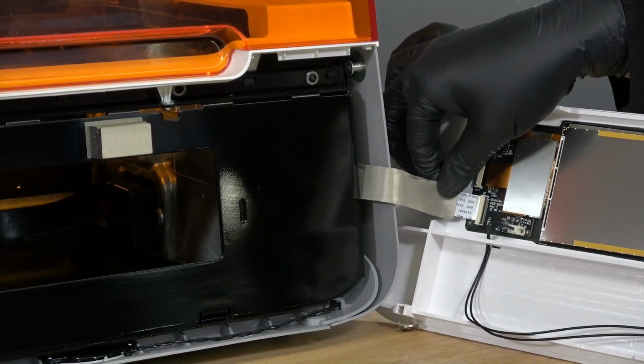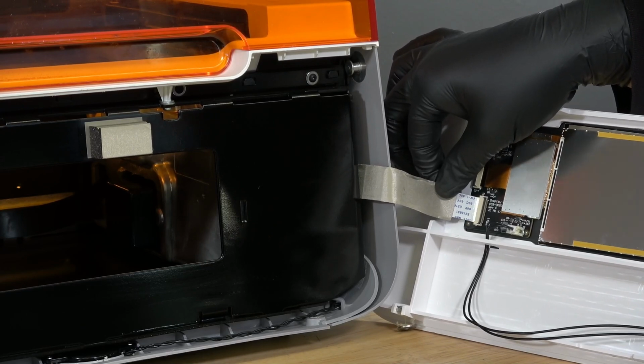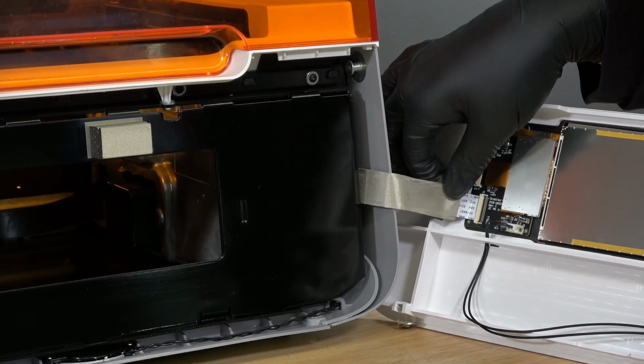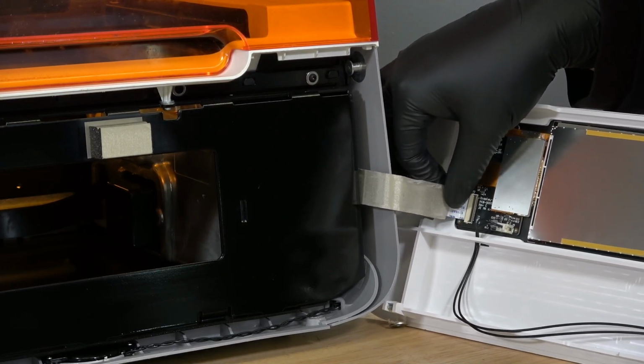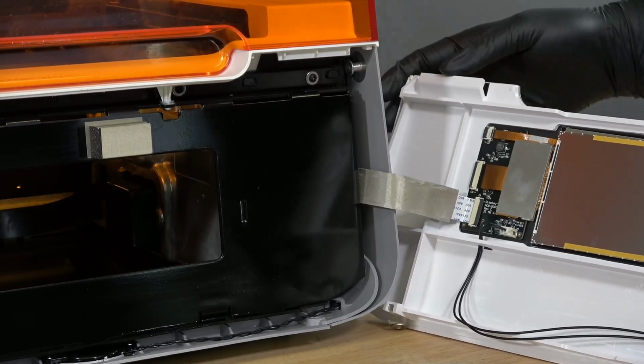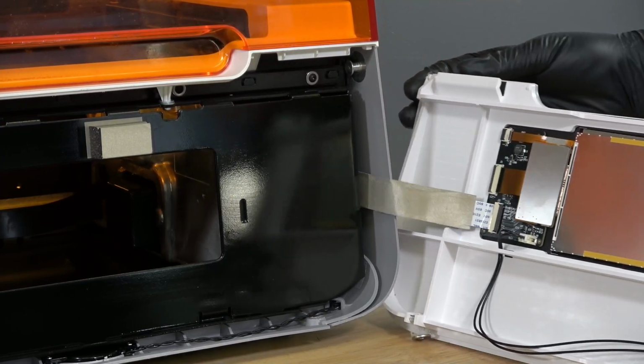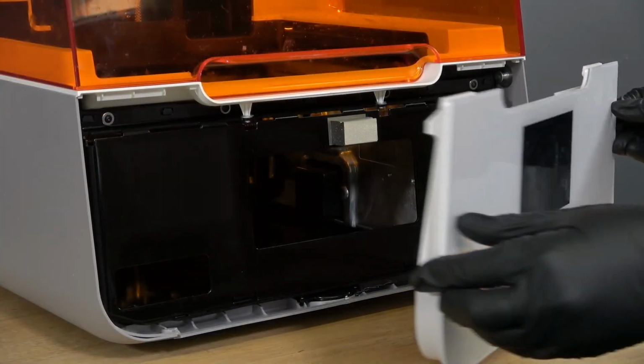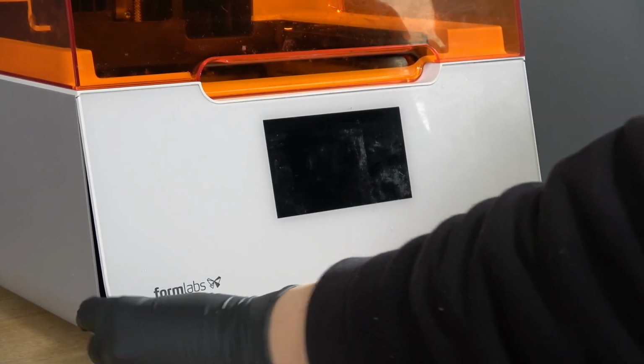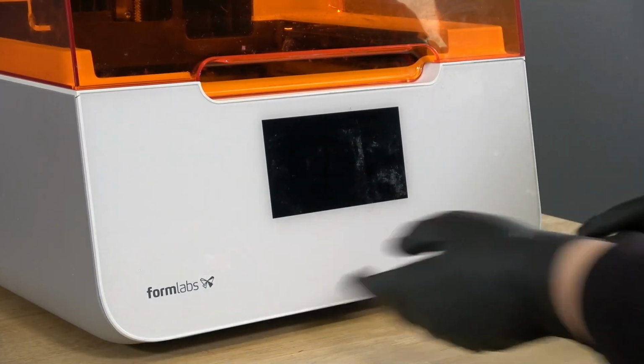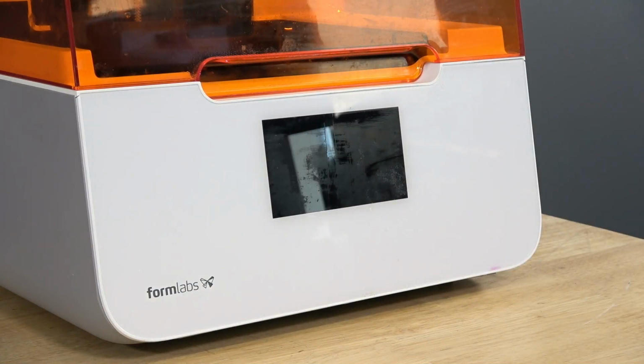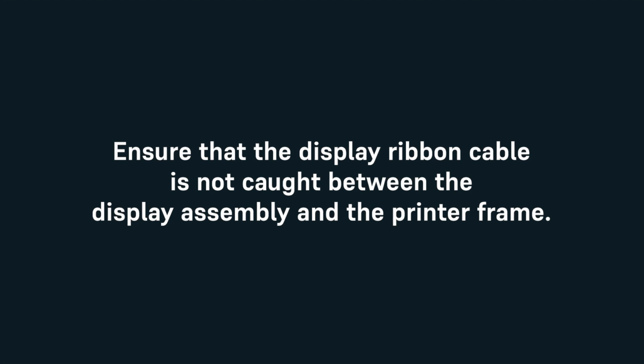Insert the display ribbon cable into the connector on the display assembly, ensuring that the ribbon cable is not twisted or folded. Rotate the latch towards the display assembly to lock the display ribbon cable in place. Insert the tabs on the top edge of the display assembly underneath the top shell of the printer. Tilt the bottom edge of the display assembly towards the printer until it lies flush with the bottom shell and side shells. Ensure that the display ribbon cable is not caught between the display assembly and the printer frame.